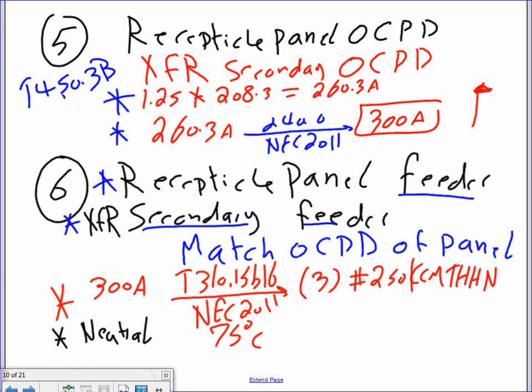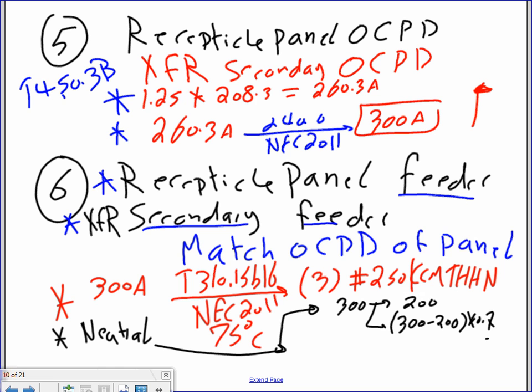The reason why I did this, Adam, is because I exceeded the 200. For the neutral, guys, here's what you need to do. Right in here, for the neutral, take the 300 amp. The first 200, leave them alone. 300 minus 200 multiplied by 0.7. I need somebody to do the math for me. So that will be 270, right? 270 amps.